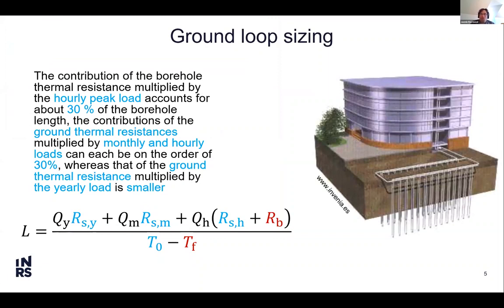When engineers and geoscientists design those closed loop systems, the idea is to find L, the total length of borehole that you need to fulfill the energy needs of a building, the Qs that are shown in my equation, taking into account the ground thermal properties and the borehole thermal properties. The ground properties are the thermal resistance of the ground, which depends on the thermal conductivity, actually. And RB is the borehole thermal property, the thermal resistance of the borehole. Considering also, at the denominator of my equation, the undisturbed ground temperature and the fluid temperature.